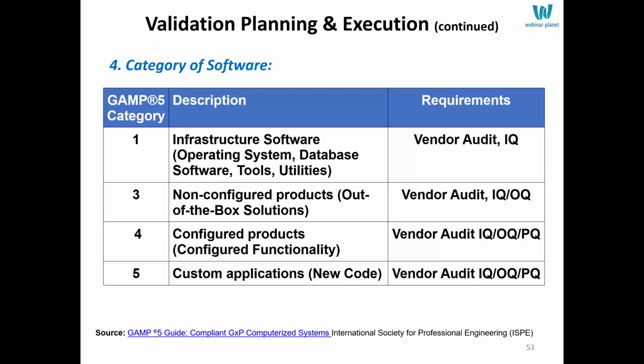So notice when you go from Category 1, where you have items that are heavily used throughout the world, say Microsoft Windows operating system. That's used so heavily in the world that if you install it correctly, you know it's going to work correctly. You know the design is correct. You don't have to go beyond that. But when you go through 3, 4, and 5, especially with Category 5, you may have a solution unique to your organization. It's not heavily road tested through the industry. It's something that you have to heavily test based on the potential risk of failure.